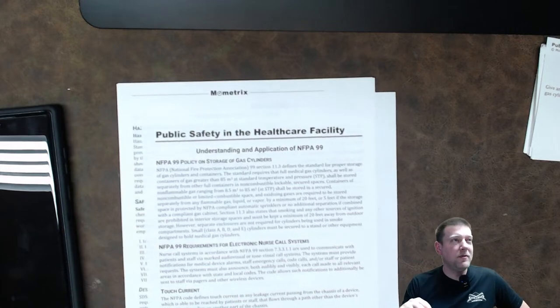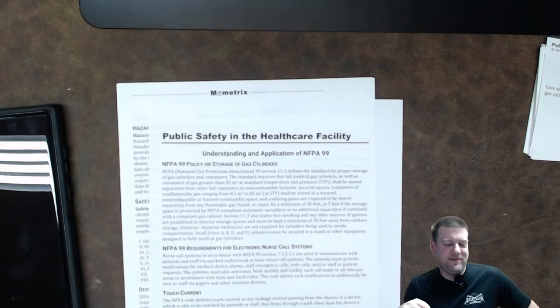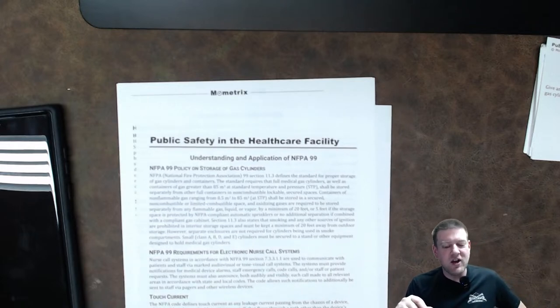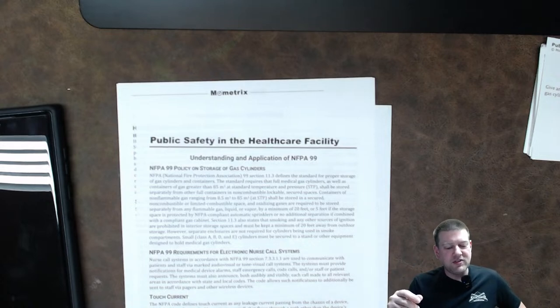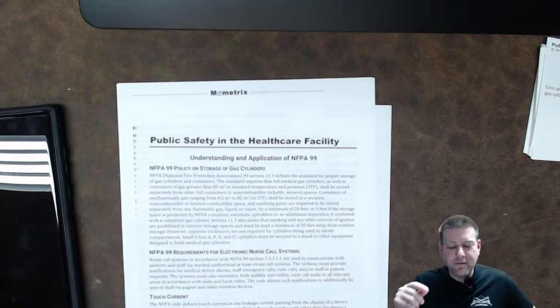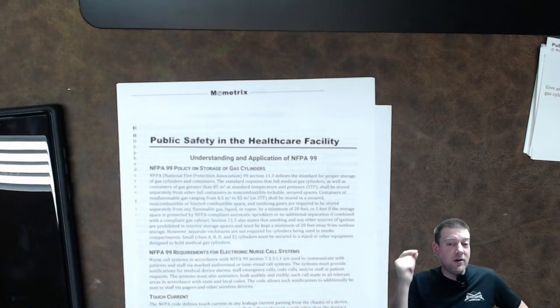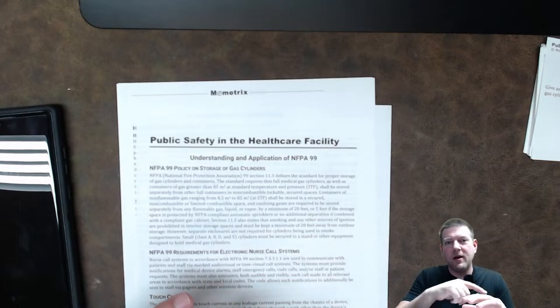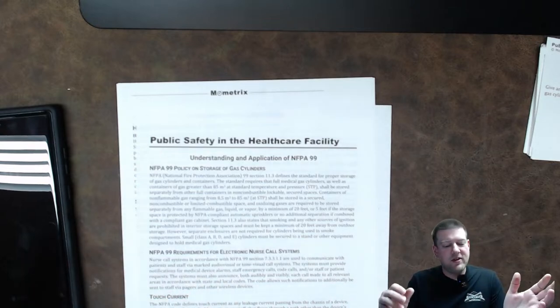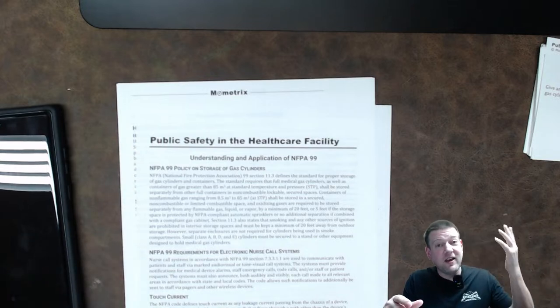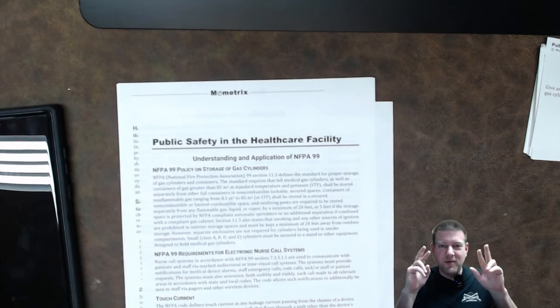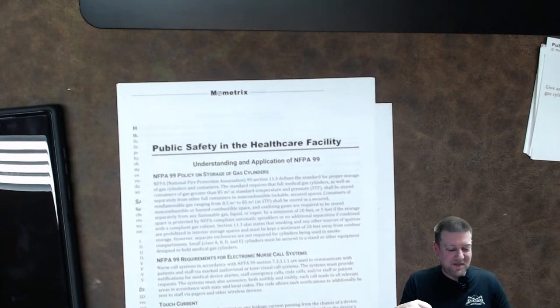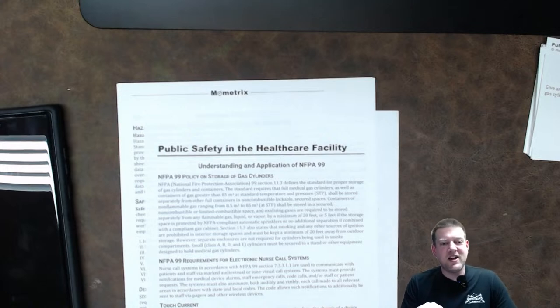We're going to get into some terminology next. Touch current. The NFPA code defines touch current as any leakage that passes from the chassis of a device which is able to be reached by patients or staff and flows through other than the device's protective grounding or another piece of the chassis. So anytime you touch a device, it's the amount of leakage that passes onto you. It's touch current. I guess that technically makes a lot of sense. I think they've called this different things. Obviously, they've called it leakage current. But touch current is the new modern and correct terminology. So, yeah, it used to be earth leakage, then chassis leakage, and now it's touch current.